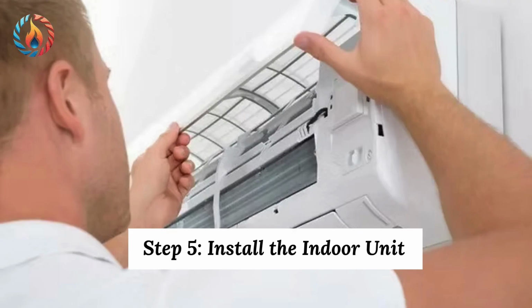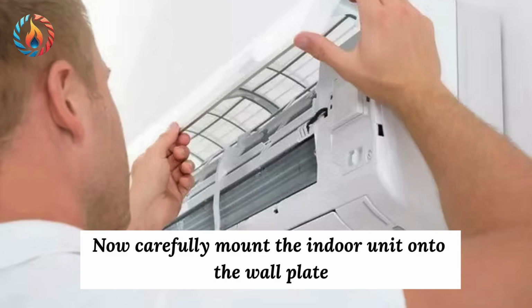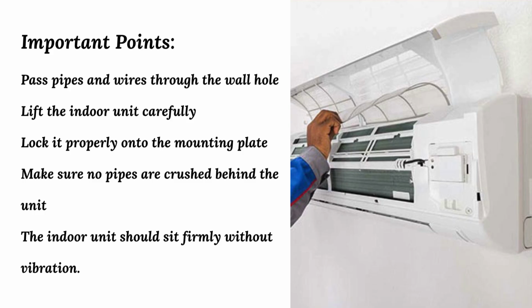Step 5. Install the indoor unit. Now carefully mount the indoor unit onto the wall plate. Important points. Pass pipes and wires through the wall hole. Lift the indoor unit carefully. Lock it properly onto the mounting plate. Make sure no pipes are crushed behind the unit. The indoor unit should sit firmly without vibration.